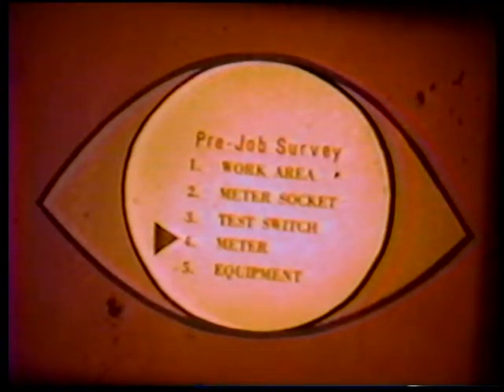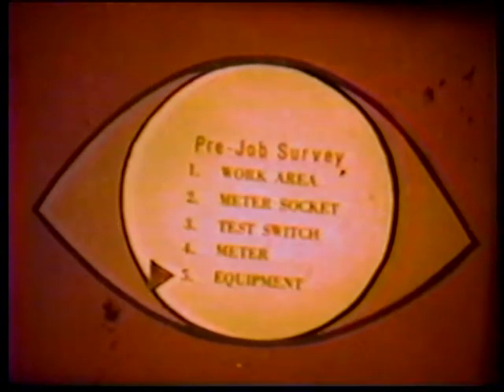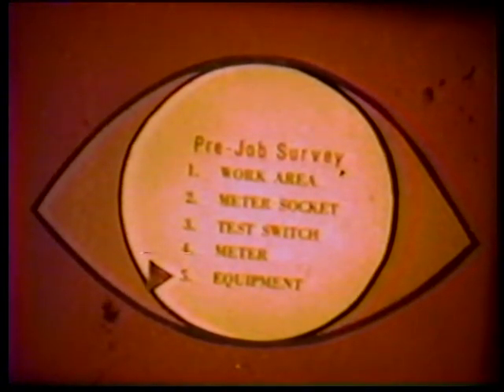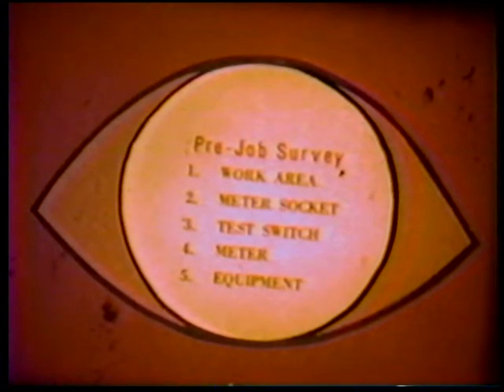Now, the meters. Is that the right meter to be used for a specific location? Check the nameplate, voltage, and type of meter. Check the condition of the glass, the seal, and the arrestor gap. Be sure you have the right equipment and material on hand to do the job safely. This completes the pre-job survey: the work area, meter sockets, test switches, meters, equipment, and material.